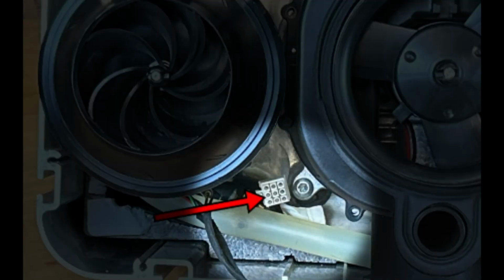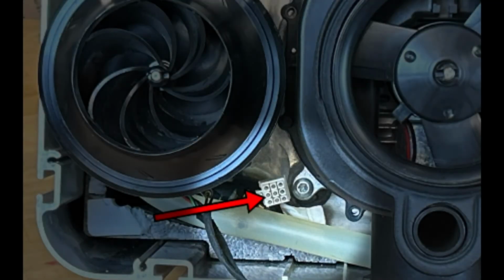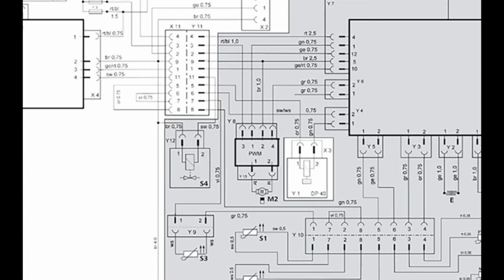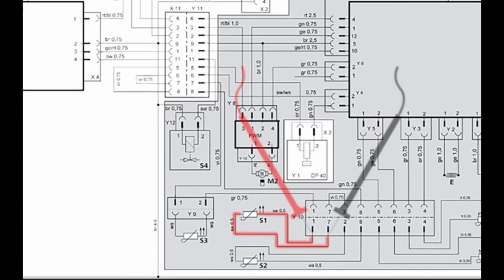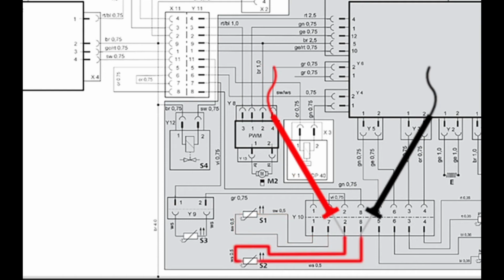You'll check those 2 wires. The air and water overheat switches can be checked through the Y10 connector. Simply check continuity between pins 1 and 7 for the water overheat switch and pins 2 and 8 for the air overheat switch.